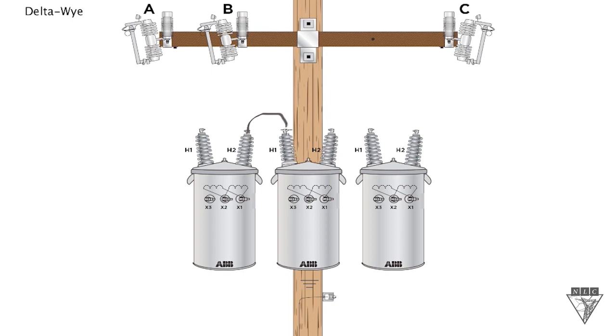So I'll start right here, got our H2 tied to the H1, this H2 tied to the H1 on that far right transformer, and then the H1 tied over to the H2 on this far right transformer. Now we're just going to connect to each phase. We'll take this H1 right here and go up to A phase, and the center transformer we'll take to H1 and go to B phase, and then the transformer on the far right we're going to take up to C phase.